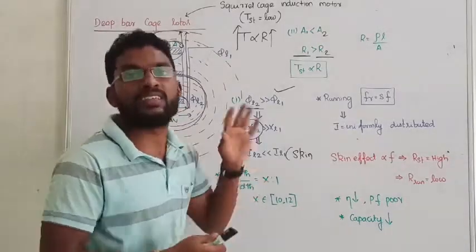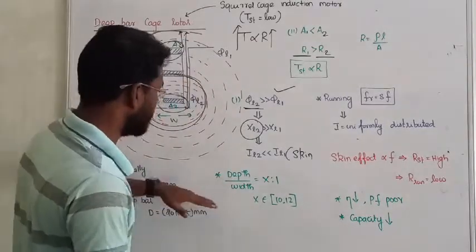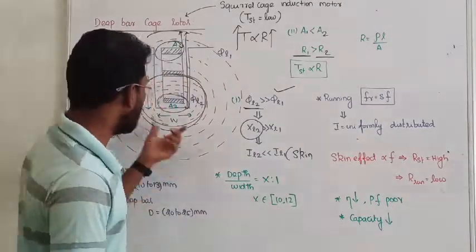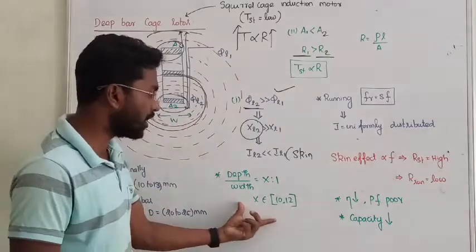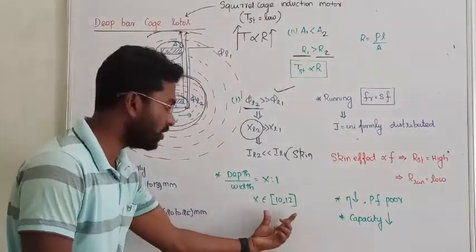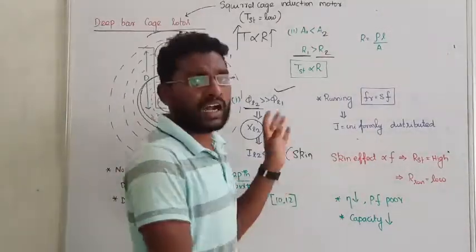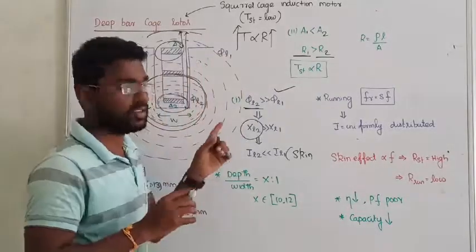In the outer surface the current is more, inner surface current is very less. So this is called non uniformity or simply called as skin effect. Depth ratio for practical construction, the ratio depth 10 to 12, that is practical construction of deep bar.